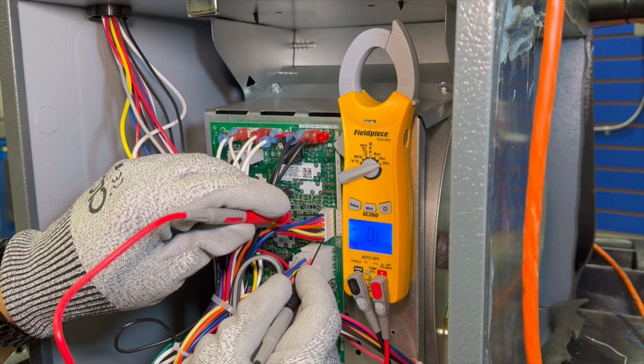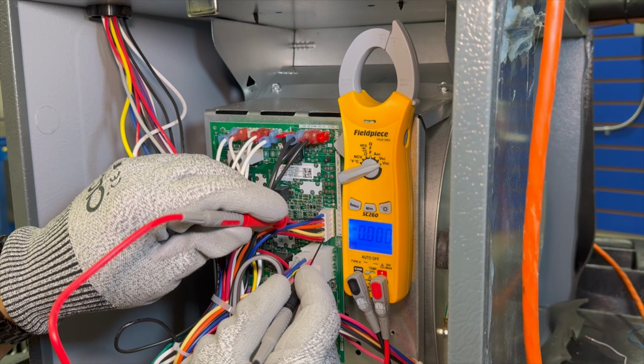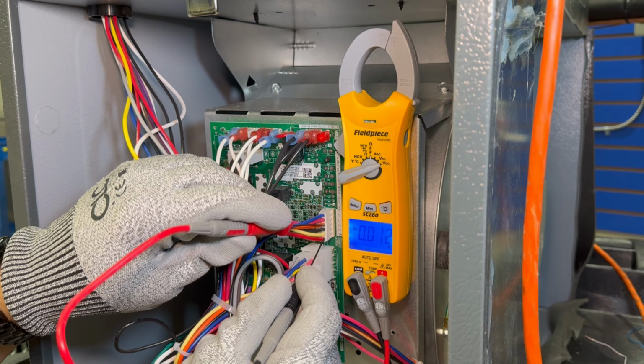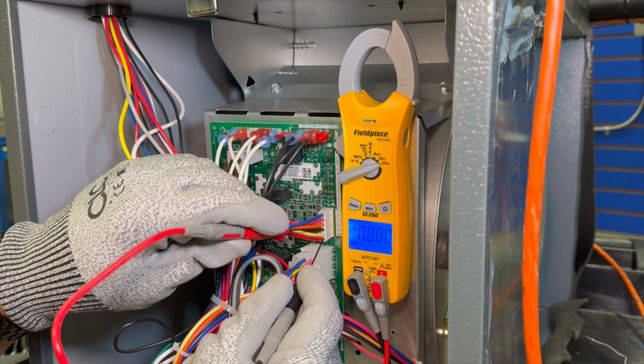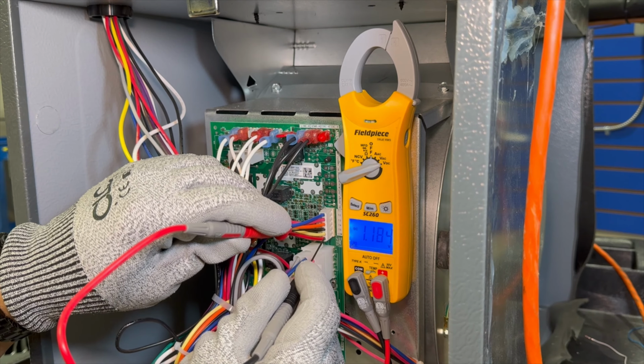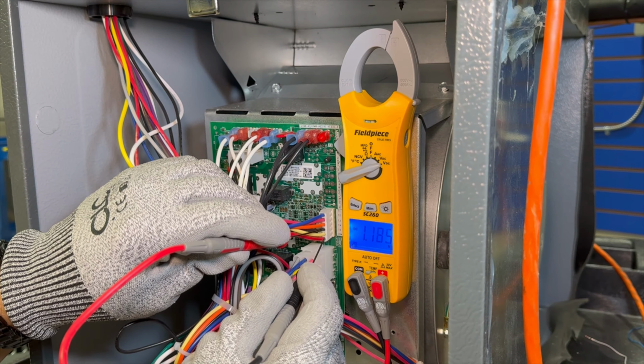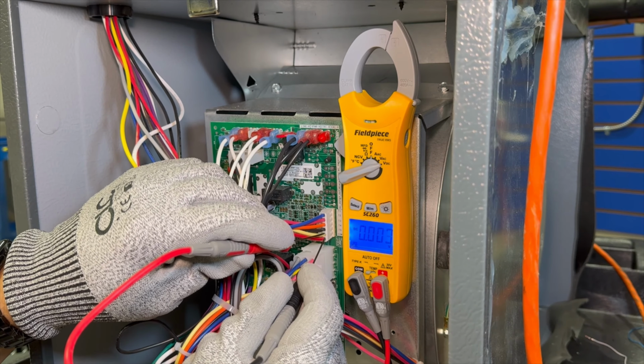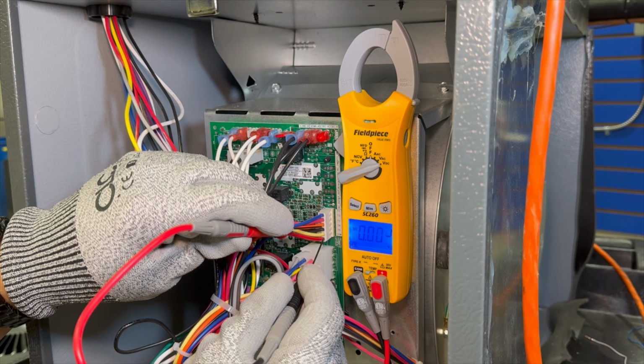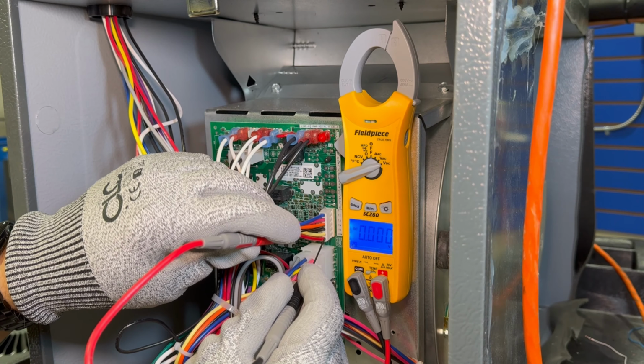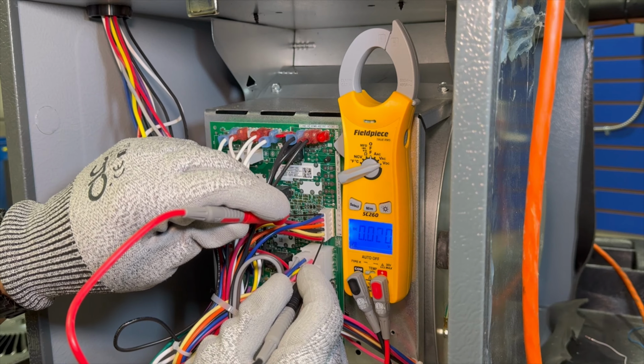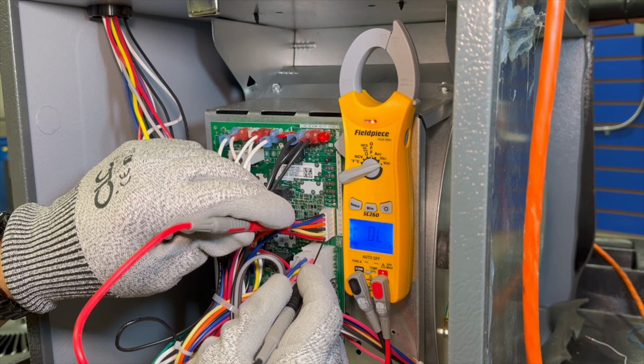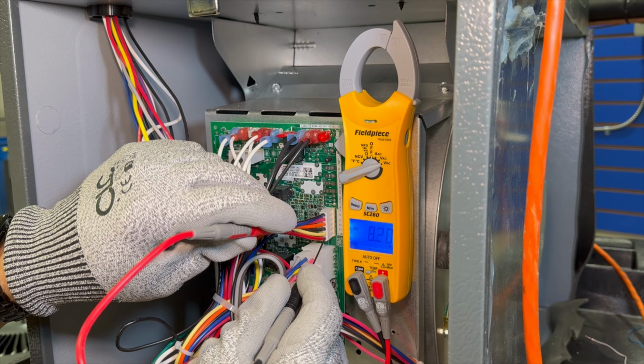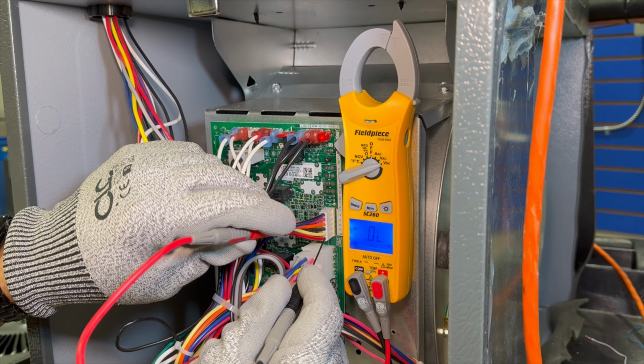8.28 volts on T1. So we're not using 24 volts AC like we traditionally thought of on our constant torque ECM motor. We are truly using a DC voltage onto terminal T1 in conjunction with common for this particular fan speed. If we were to change the fan speed, say we introduced a call for cool, it would actually move the DC voltage to a different terminal.